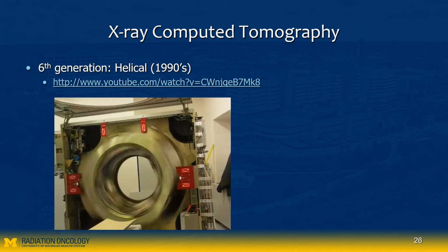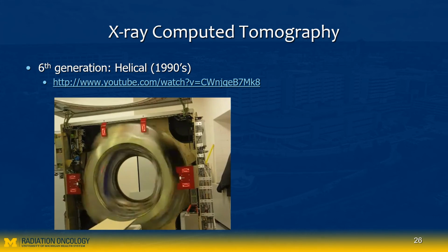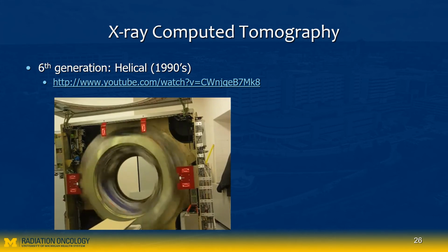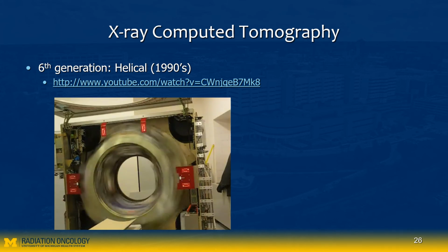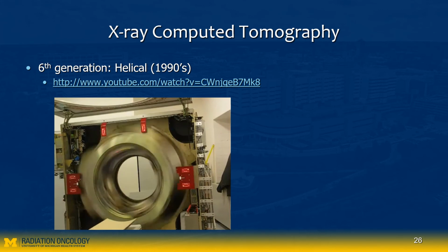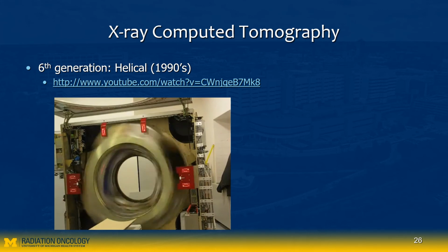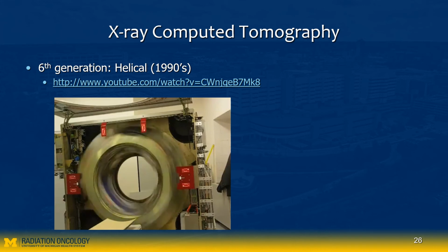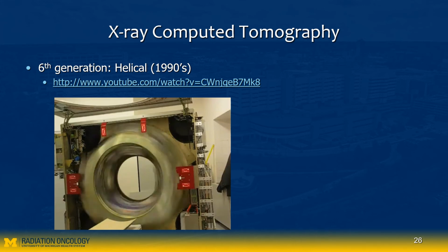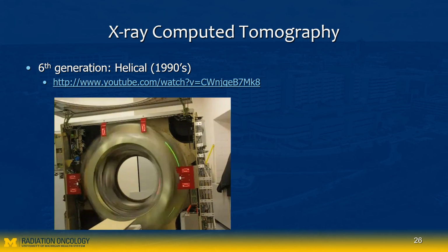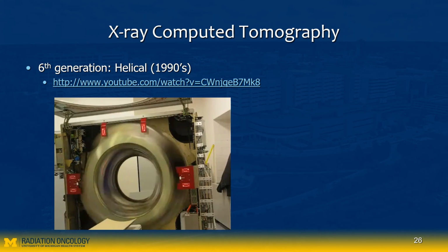Then it can be really fast. So the faster the gantry rotates, the less of a motion artifact it will create, right? A lot of things are moving inside the patient body, like breathing motion and abdominal motions, but with this fast rotation of the gantry, you can overcome certain motion artifacts.